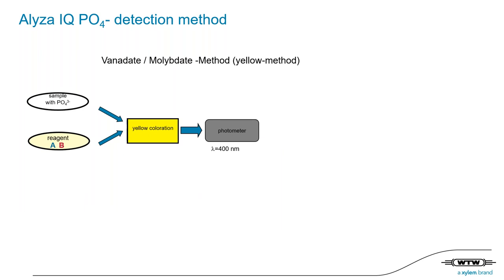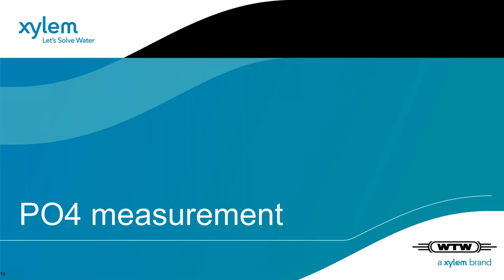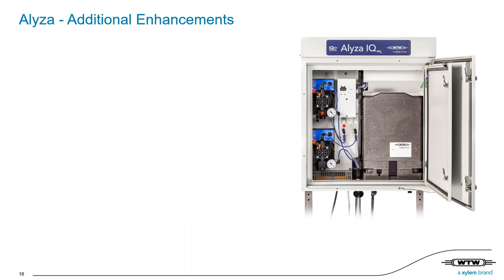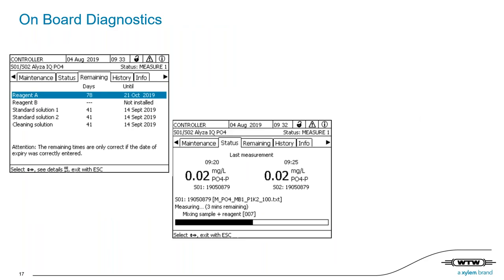So sorry, it's a little bit slow to go back. Should be here. So you see here the overview. So this is the optimized interface, so maintenance, the status, and the remaining. So you see reagent A lasts 78 days, so you would have to exchange it the 21st of October. Here you have no reagent B, standard solutions 41 days. So either with a long lifetime, you could buy a spare, of course, or you see always here, if it's only 30 days left, you can easily order a new one and you will get it in time. So this is up to you.